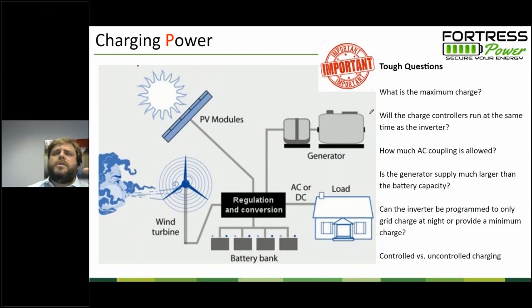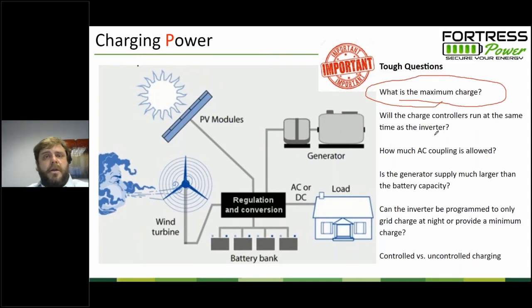And so when you're looking at charging power, what you're looking at is the maximum amount of amperage that will go into the battery. So almost the opposite of looking at the discharge rating of the inverter and the discharge rating of the battery, you need to say, hey, I have 2 eVolts, and each eVault is capable of 180 amps. And so my maximum charge rate is 360 amps. And so if I have a 100 amp charge controller and another 100 amp charge controller and a 100 amp inverter, all 3 could be on at the same time, and that's not a problem.